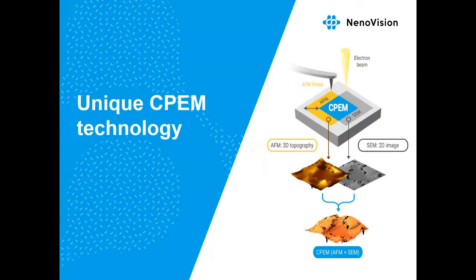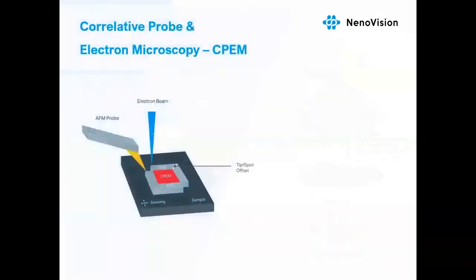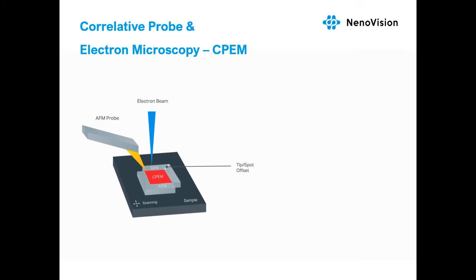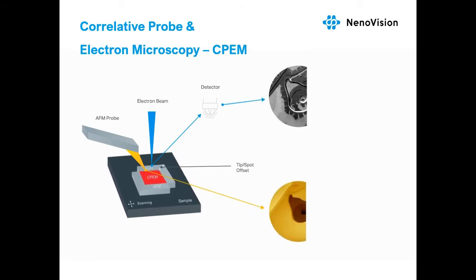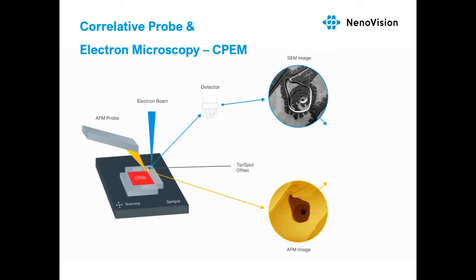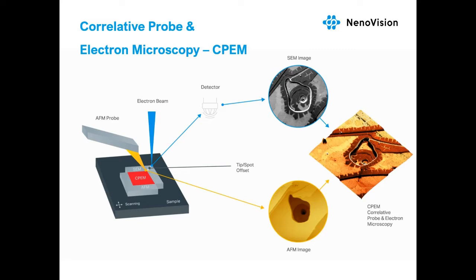As we were talking about different techniques and different applications, we didn't quite mention how the unique correlative probe and electron microscopy technology, shortly CPEM technology, actually works. So on the sample, the electron beam points very close to the AFM probe, AFM tip. During scanning, the AFM tip and the electron beam remain static, so sample is being scanned only by the LiteScope piezo scanner. This enables simultaneous detection and acquisition of AFM and SEM signals at the same time, in the same place and under the same conditions. This technology is unique to LiteScope and was developed for seamless data correlation.